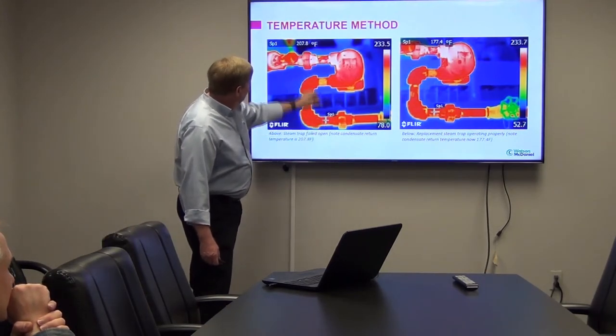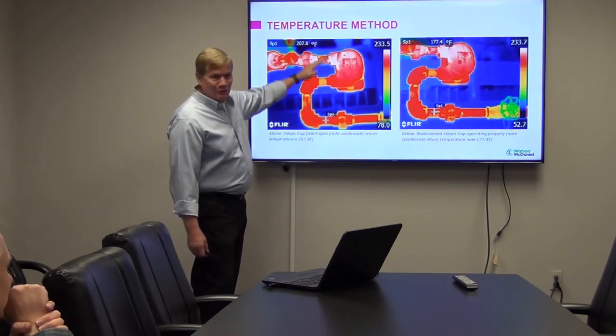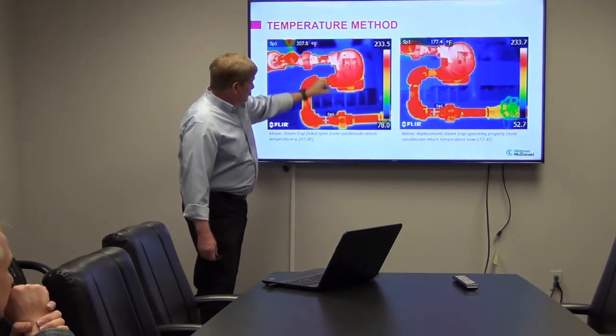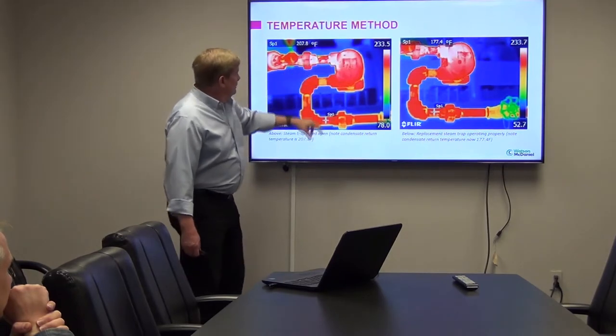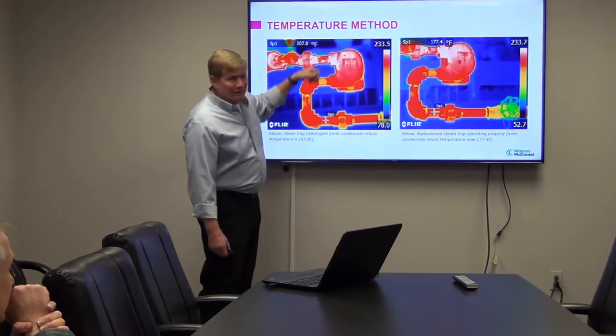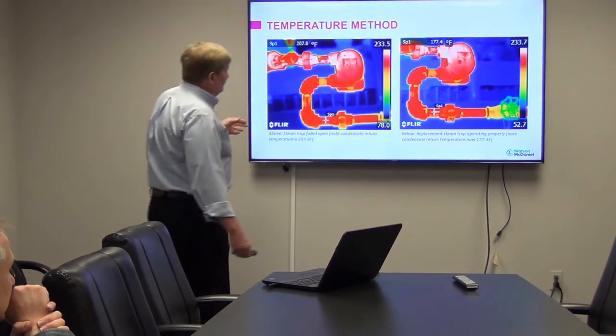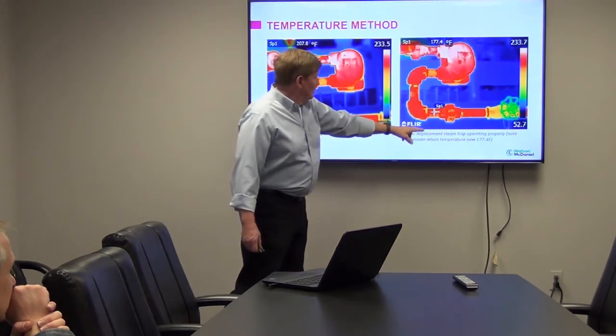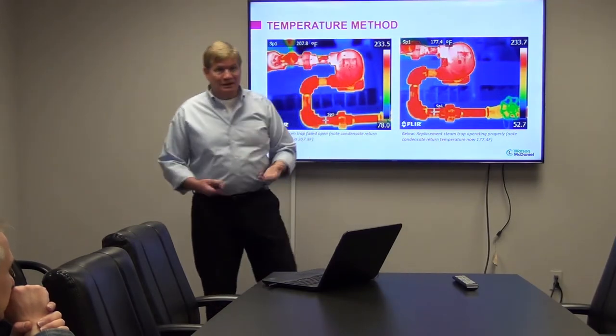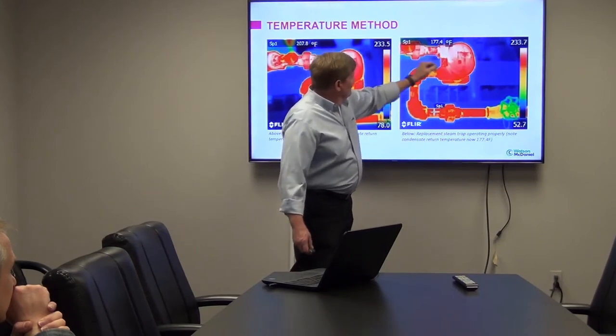So they're saying down here my temperature is 200. So they're saying that's too high. It's not holding the condensate back to allow it to subcool and allow my temperatures to drop. Normally on here, what we used to do years ago is actually put a temperature sensing device right here. That way you can actually see how the traps are operating. Because on a float thermostatic trap, now this one it says operating properly at 177 degrees F on the discharge. Okay, that's good. You could also, if you wanted to, test it right here at this point.